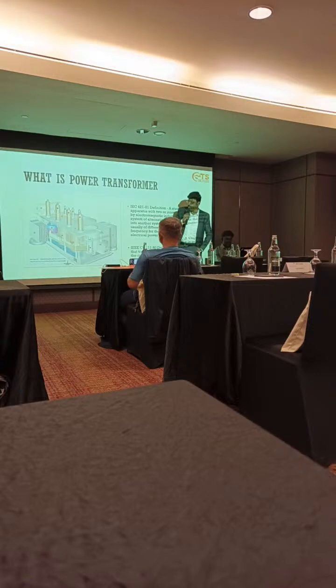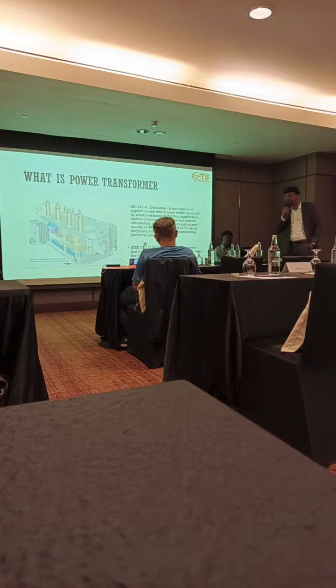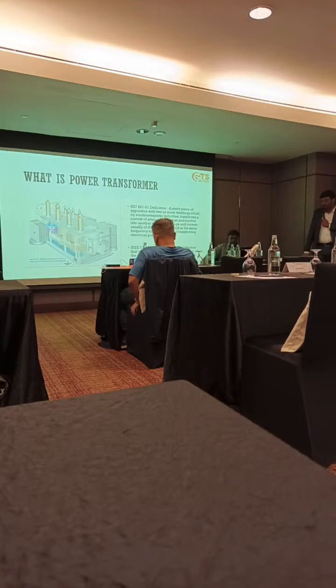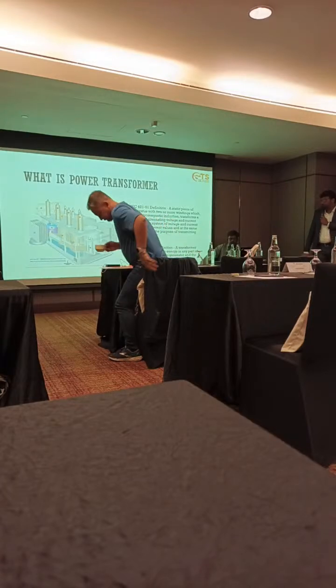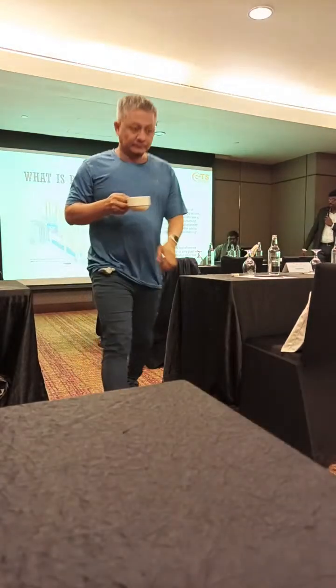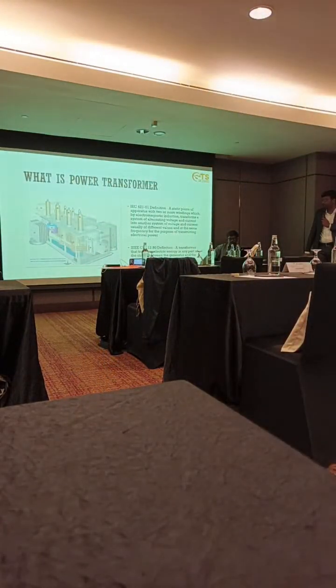This is the definition of the transformer as per the IEC as well as the IEEE standards, which, as everyone knows, defines it as a static apparatus having two or more windings, which transforms the voltage. The frequency will remain the same, sorry. It will transform the voltage alone. This is the definition of the transformer.